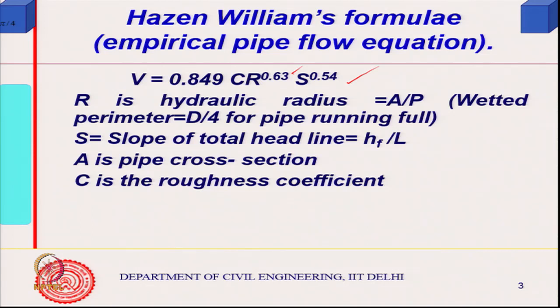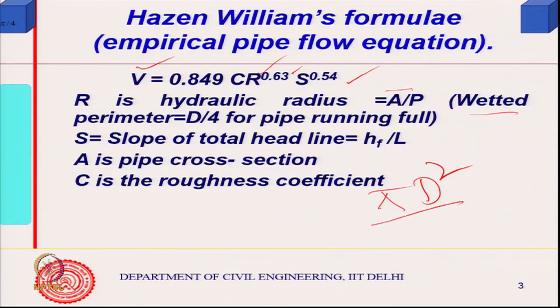In the Hazen-Williams equation, V is the flow velocity and R is what is called hydraulic radius — area divided by wetted perimeter. In the case of a pipe running full under pressure, the area is πd²/4 and the wetted perimeter is πd, so the hydraulic radius is simply d/4 for a pipe running full.